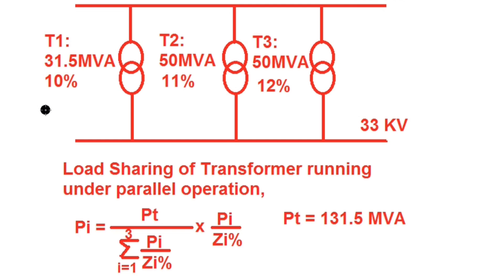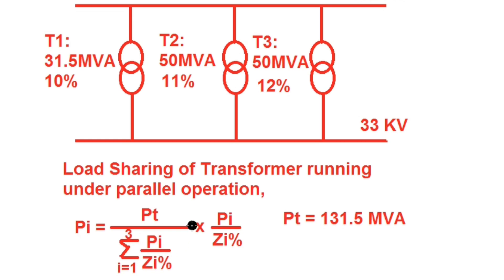Load sharing of a transformer is proportional to its MVA capacity and inversely proportional to its percentage impedance. The load shared by the i-th transformer is given by: Pi = PT divided by the summation (i=1,2,3) of Pi divided by Zi_percentage, multiplied by Pi/Zi. Here PT is the total load of the substation, equal to 131.5 MVA.